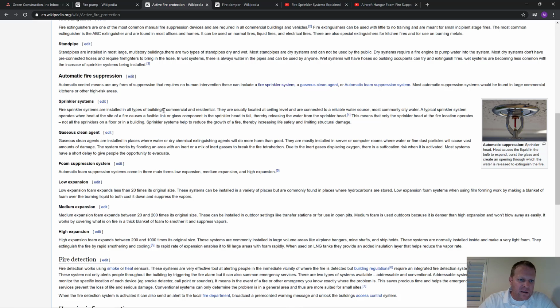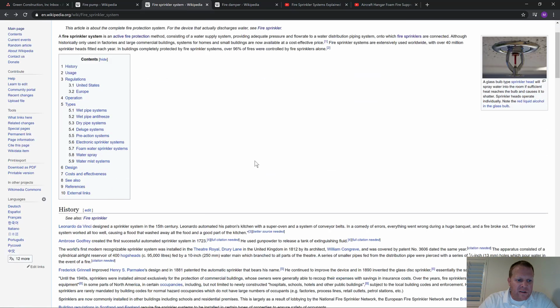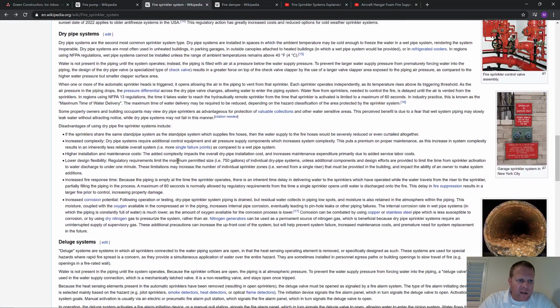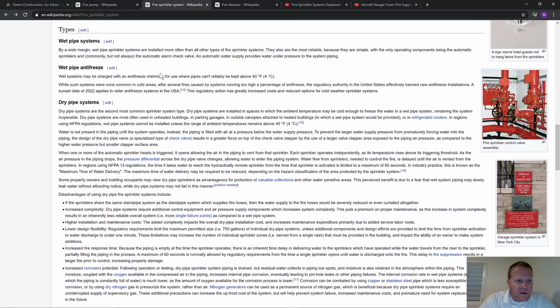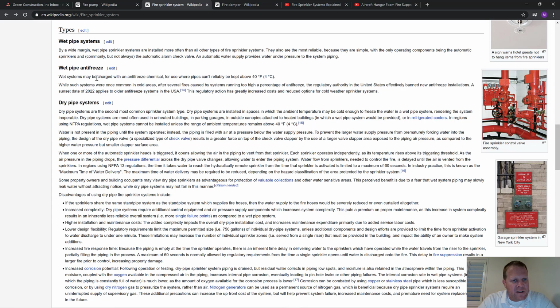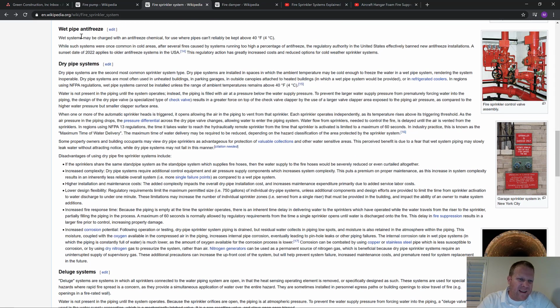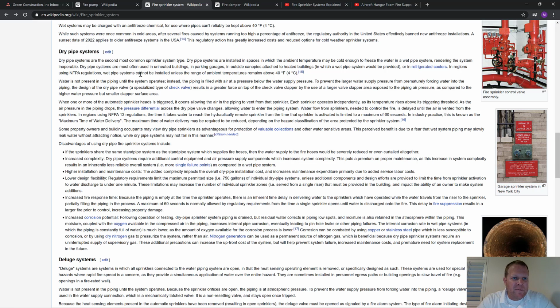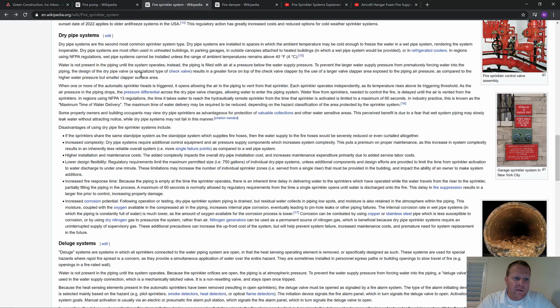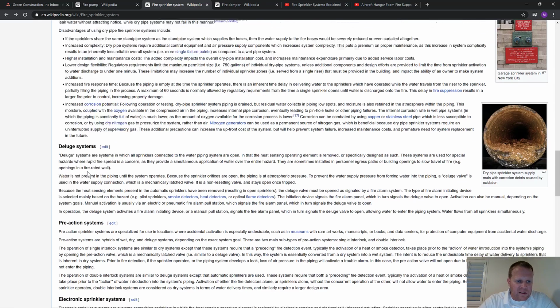Let me go back to Wikipedia. I wonder if I had it here. We had the terms pre-action. Let's see if they have it here. Here we go. Dry pipe systems, wet pipe systems with antifreeze. So you have the wet pipe system, and you have the wet pipe with antifreeze. I see that a lot when the sprinkler is wet, but then they put piping up in the attic or something like that, and they'll just fill that section of pipe with antifreeze. And antifreeze is not just straight antifreeze, it would have water in it as well. And you have the dry pipe system that we were just talking about, where they're filled with air, and then the little bulb gets broken, and that pressure drop indicates, hey, I need water on that control valve. The control valve opens up and sends water to it. And then you have the deluge system.